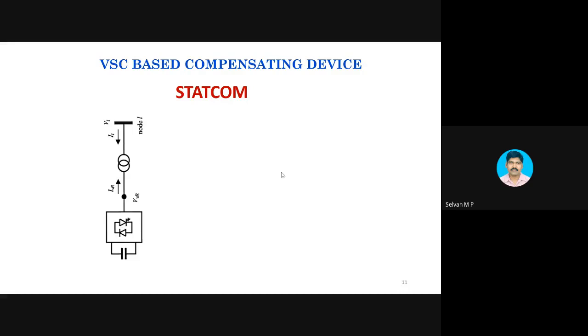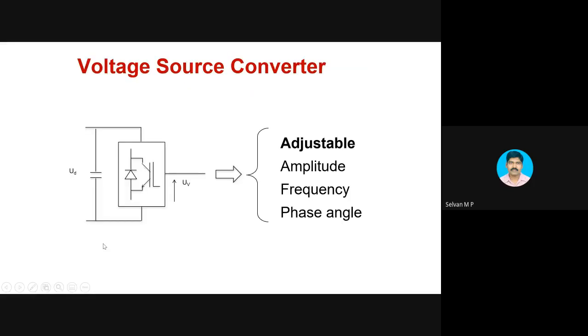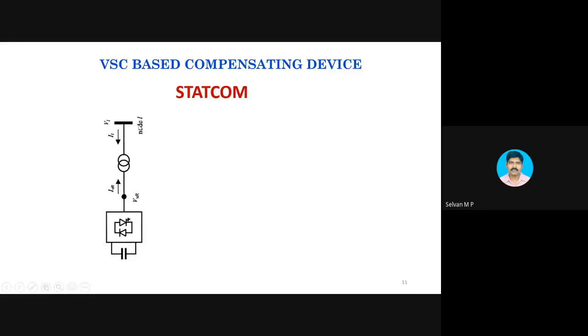that we will see here. So now I have a voltage source inverter, right? And this is not a thyristor, it is a GTO, gate turn off thyristor. A gate turn off device can operate like an IGBT, which is a self commutating device, not like a thyristor, which is a forced commutation device. So I can use a GTO or an IGBT depending upon the power level. It is a voltage source inverter, which I have shown here in this slide, connected to the bus through a transformer.